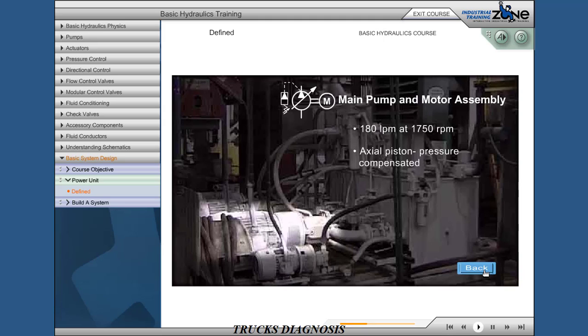Main pump: 180 liters per minute at 1,750 RPM. Axial piston pressure compensated. Provides system flow. Compensator set at 100 bar.